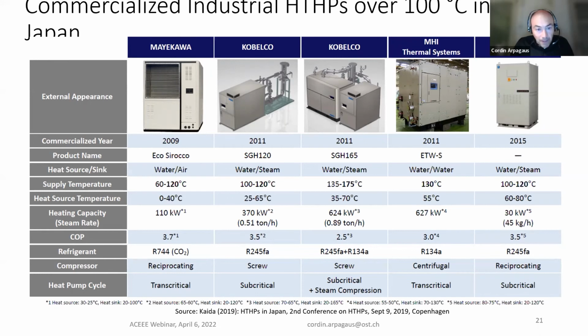You can also see, for example, the cycle type in the lowest row: transcritical or subcritical. Transcritical is a cycle where the refrigerant - in this case for Maekawa it's CO2, a natural refrigerant - operates in transcritical conditions. That means it is very suitable for processes to heat up a stream, for heating up processes.